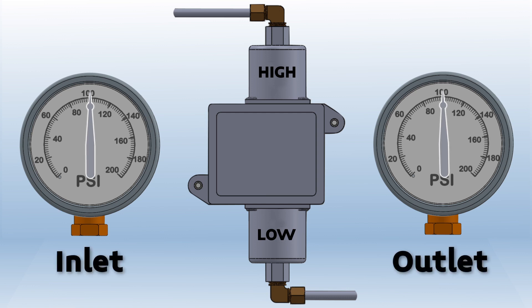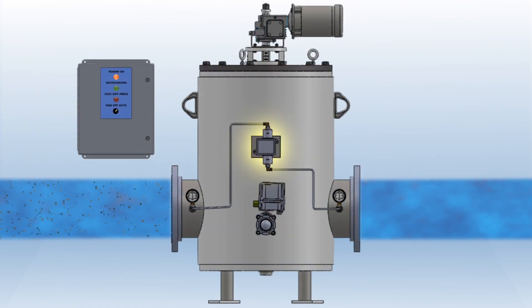As the screen becomes blocked, the inlet pressure will begin to rise over the outlet pressure. Once the pressure differential hits the set point, the differential pressure switch sends a signal to the control panel to initiate a cleaning cycle.